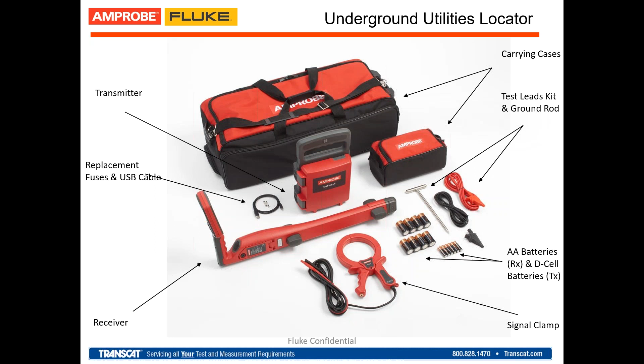Now, that said, I mentioned two different modes, right? I mentioned passive mode, or modes where you use the receiver and the current is already flowing on the circuit. And we call that type of method passive signals. Passive because the electricity is generated passively by a third party, whether it's a utility or an industrial plant, right? They're already injecting active nominal voltage at 50 or 60 hertz, right?